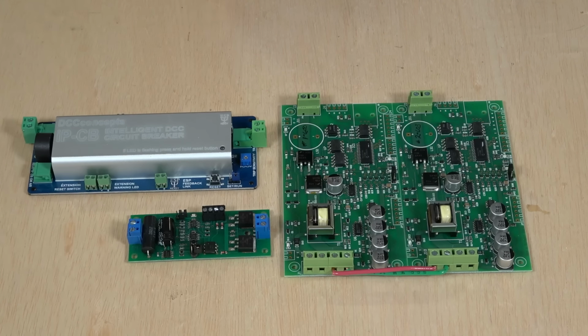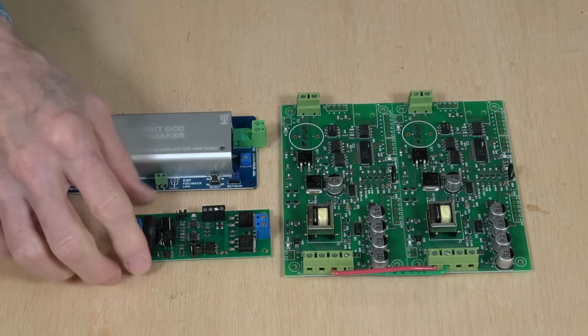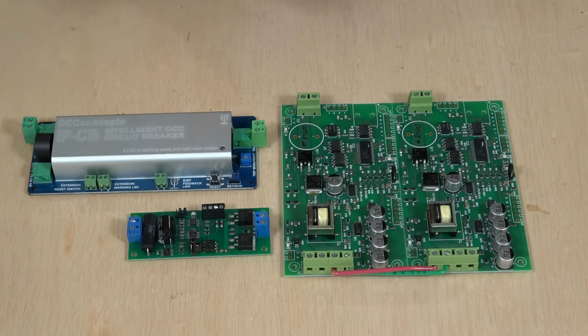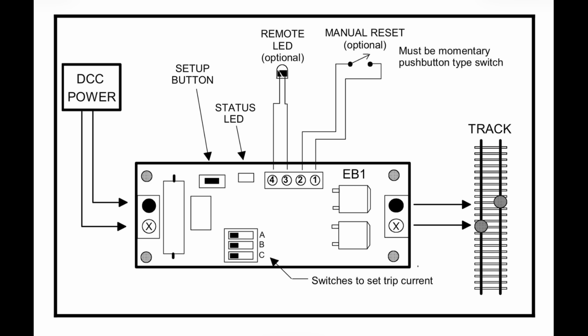Okay, let's take a look at that diagram for this guy right here, for the EB1. Okay, so looking at this, you can see at the bottom, they show you the switches that are available for setting your trip current. And this is from the instruction sheet for the one that has the dip switch, as opposed to the jumpers that I showed you on mine, which is a slightly older unit.